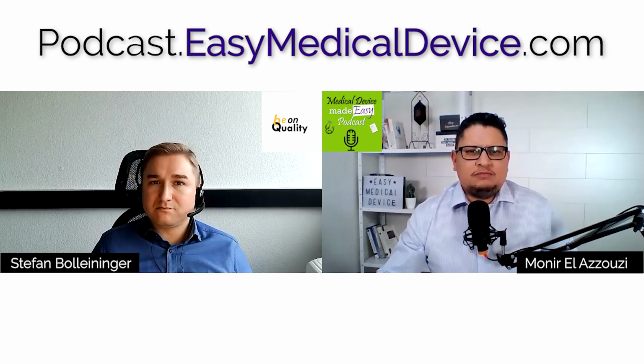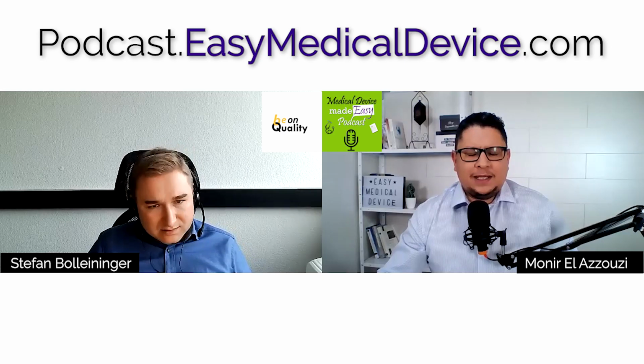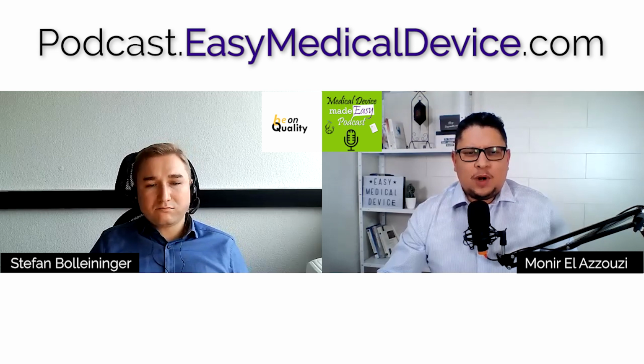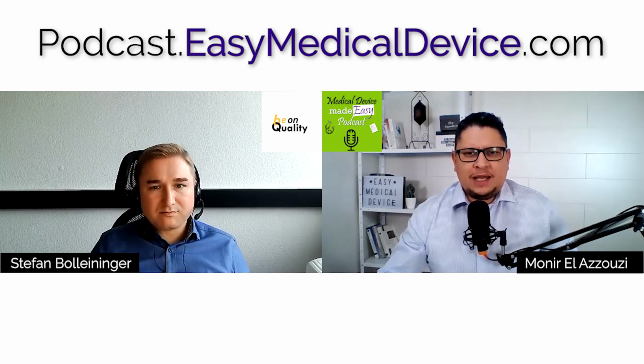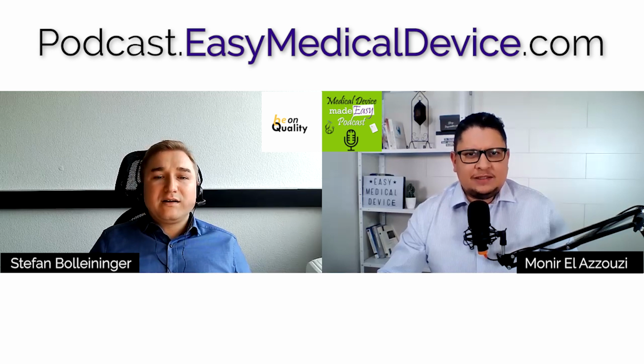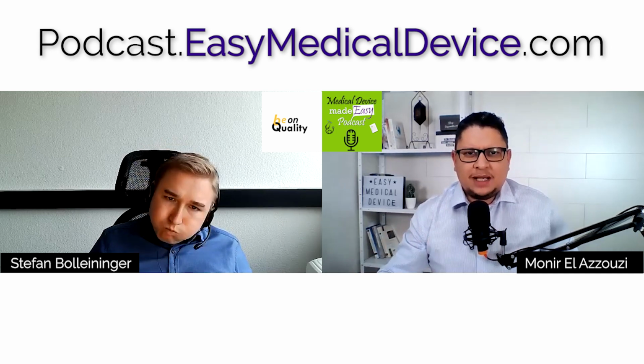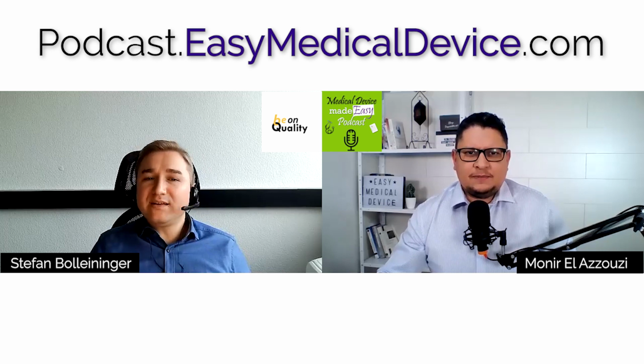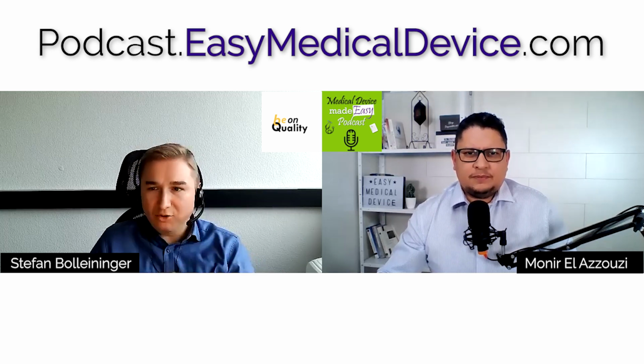Okay, so it means that every hospital in the European Union can reuse single-use devices if they have the right studies, if they have the right elements to prove that they can do that, even if the manufacturer is saying that this is a single-use device. Is that really the right interpretation of this? That is correct. Okay. But there's always a catch.